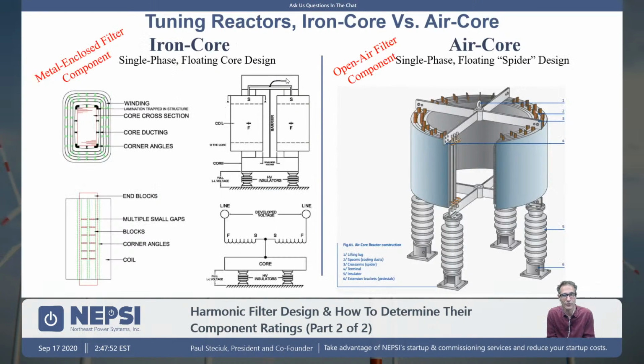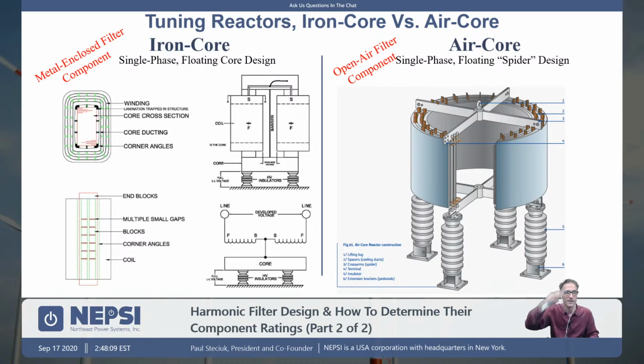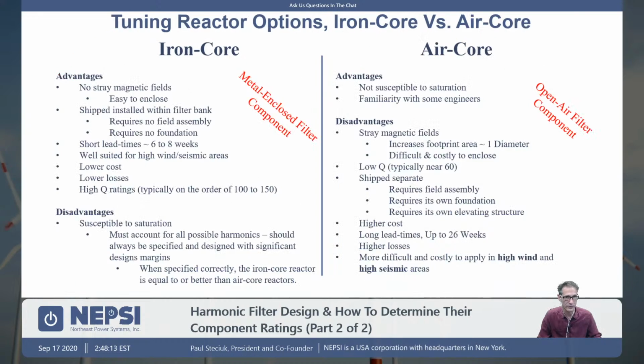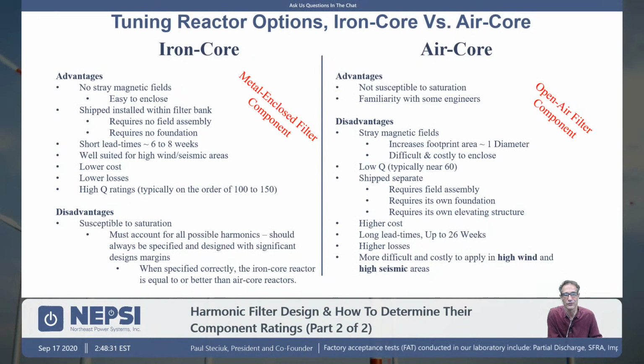The only difference is that the iron core is also conducting the magnetic field, whereas in an air core reactor you're using air. Because you're using air to develop the inductance, you need a lot more turns. So typically these reactors are very large in diameter, and they're very high, and they have a very high magnetic field around them. So these are things that you need to be concerned about. So we'll go through the advantages and disadvantages of the iron core and air core designs. With iron core reactors, there's no stray flux. They are shipped installed within the filter system. If you go with air core reactors, the reactors are so big there is no shipping them as part of the harmonic filter bank. They're shipped separately and installed on site.